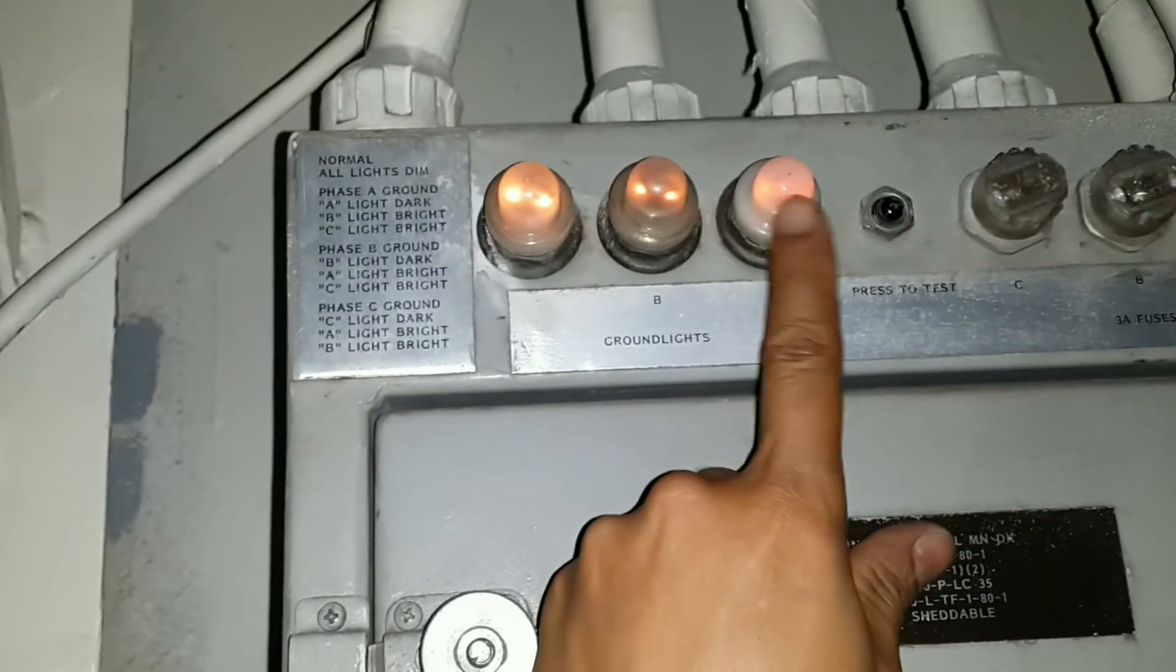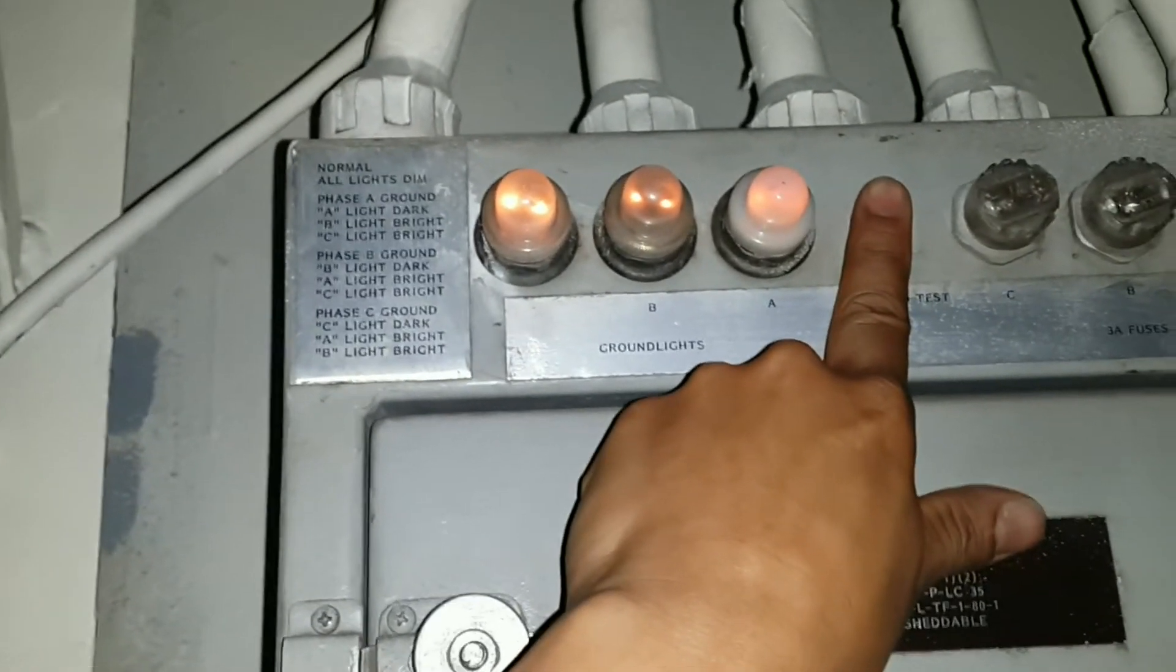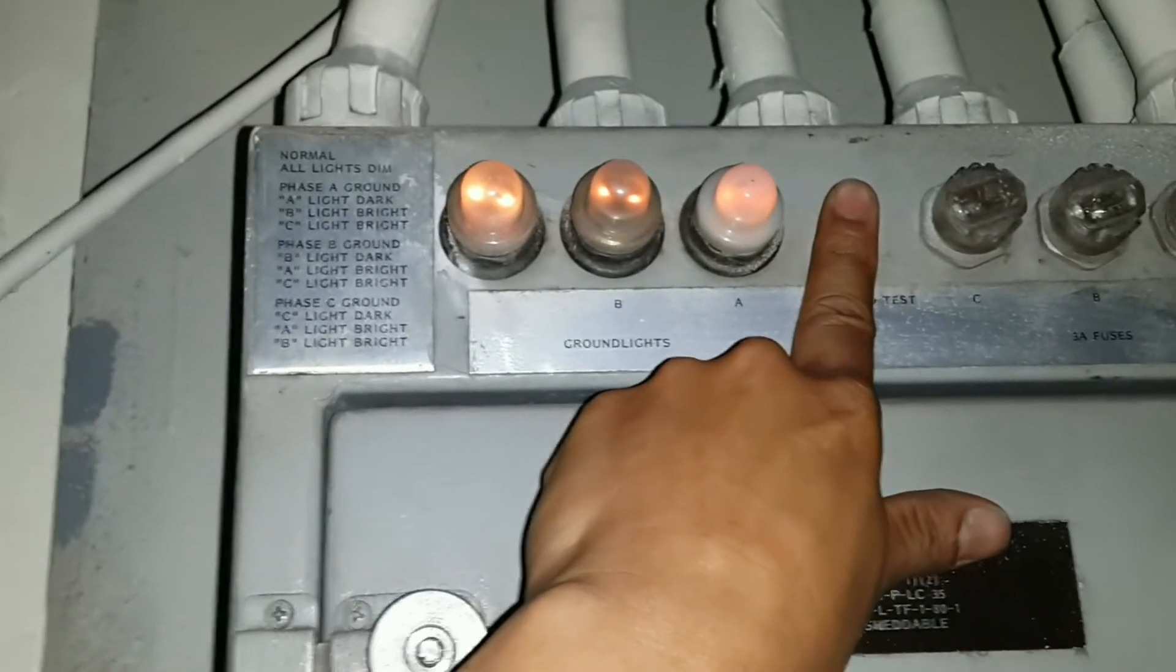Here I got a 120 volt power panel, and I got a light indicator. If I press the button, and if one of those lights had gone out, I would have a ground in that phase. But this one passes the test.